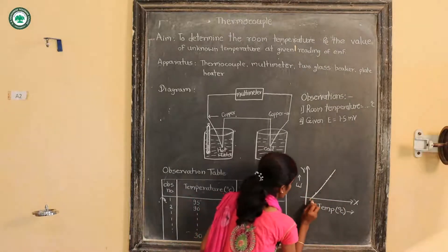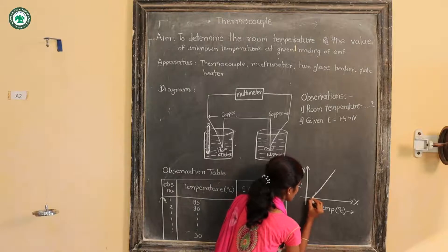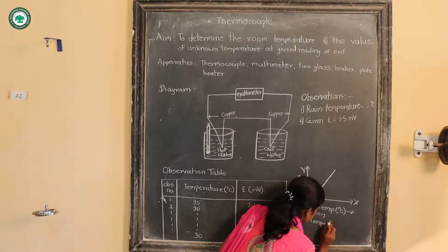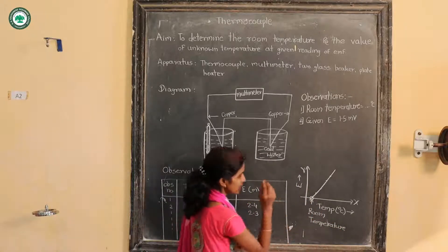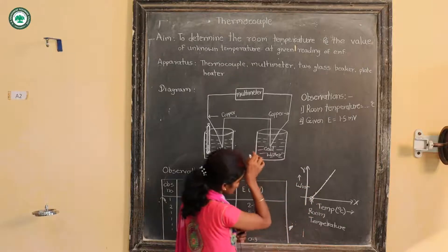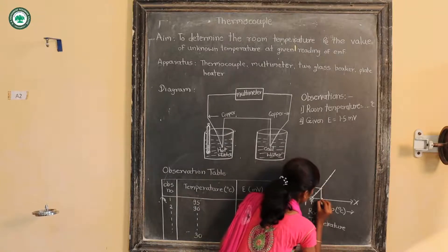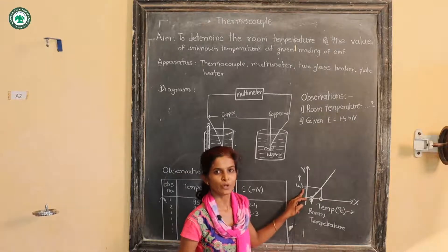One has to verify the room temperature from the graph. This graph will cut the x-axis at a certain temperature, and that temperature is the room temperature. Also, one has to determine the temperature corresponding to 1.5 millivolt EMF. One draws a perpendicular from that EMF value on the graph and then drops another perpendicular to the x-axis to read the corresponding temperature.